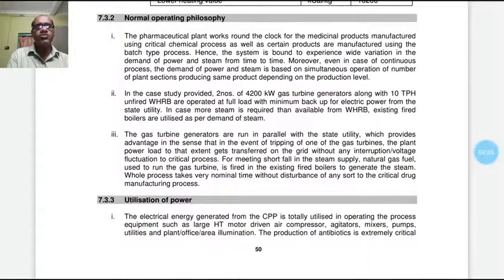In the case study provided, two 4200 kilowatt gas turbine generators along with 10 TPH unfired waste heat recovery boilers are operated at full load with minimum backup for electric power from the state utility. In case more steam is required than available from the waste heat recovery boiler, existing fired boilers are utilized as per demand of steam. The gas turbine generators are run in parallel with the state utility, which provides an advantage in the sense that in the event of tripping of one of the gas turbines, the plant power load to that extent gets transferred to the grid without any interruption or voltage fluctuation to critical processes.